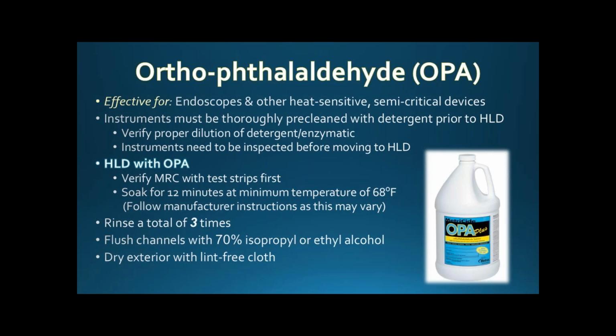But a big part, especially if you have a Joint Commission survey, is that the test strips and the logging and documentation of your test strips are very, very critical. You need to make sure that you have those 3 positives and 3 negatives tested with the OPA for the test strips to validate them, making sure that the lot numbers match up on your documentation as well as what's on your actual bottle, dating those appropriately.